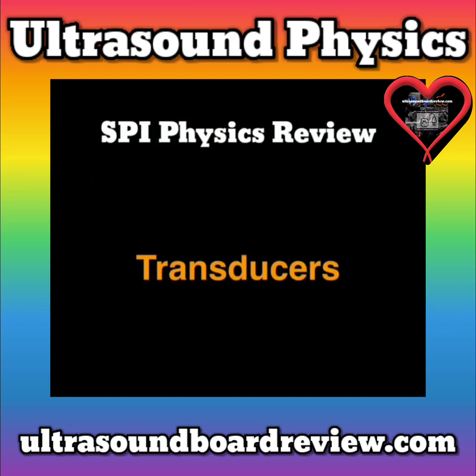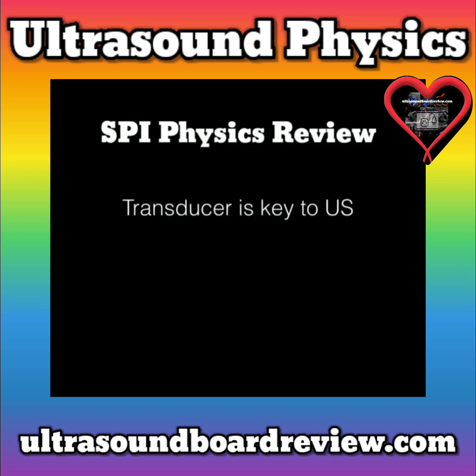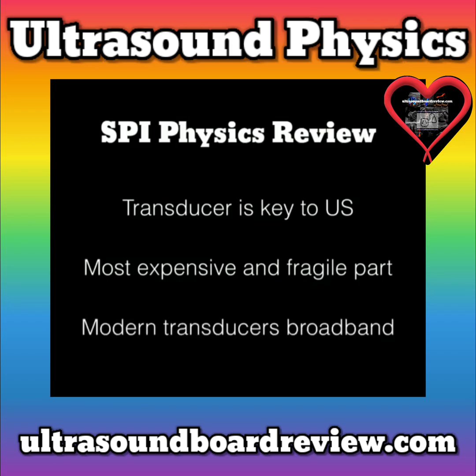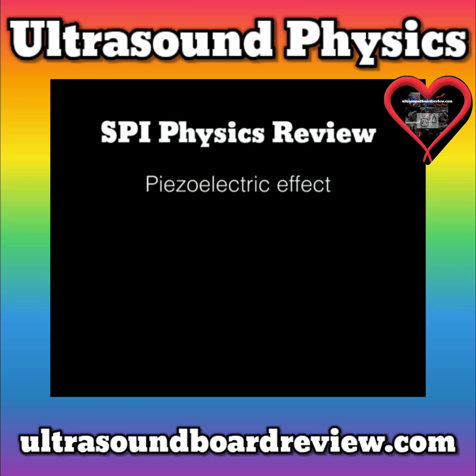There are different types of transducers that you will interact with. And the transducer is one of the key components of the ultrasound system. It is also the most fragile and expensive portion of the system. Modern transducers have a broadband designation, meaning they can image over a range of frequency. The probe is what drives the piezoelectric effect. An electrical signal comes in, activates the crystals, which then transform the electrical energy into a mechanical energy or a mechanical pressure wave, meaning sound, and transmits that sound. That sound is then transformed by the crystals back into electrical energy for the system to interpret into an image.